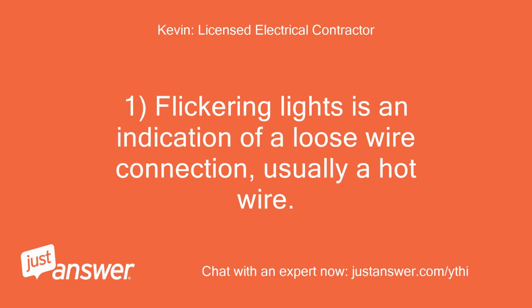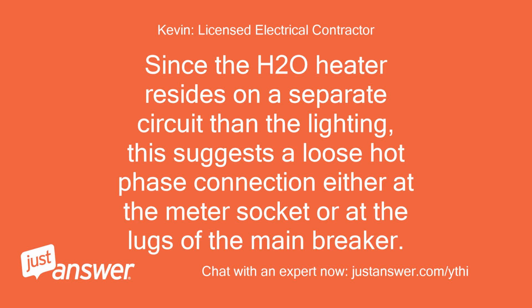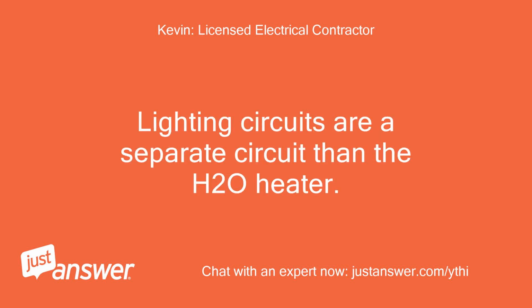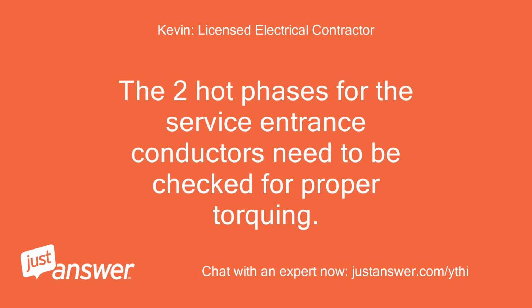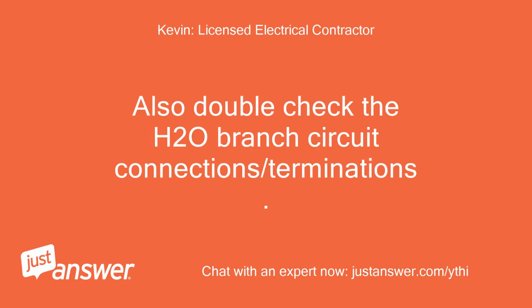1. Flickering lights is an indication of a loose wire connection, usually a hot wire. Since the H2O heater resides on a separate circuit than the lighting, this suggests a loose hot phase connection either at the meter socket or at the lugs of the main breaker. Lighting circuits are a separate circuit than the H2O heater. The two hot phases for the service entrance conductors need to be checked for proper torquing. Also double-check the H2O branch circuit connections/terminations.